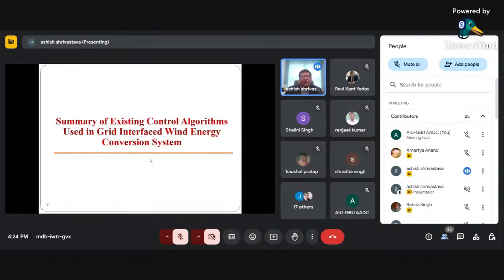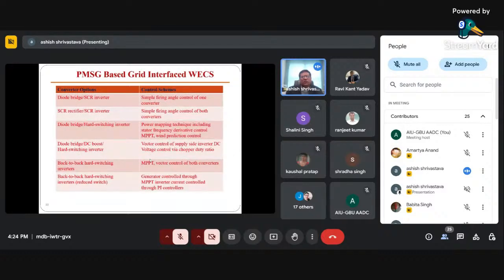So let me summarize the existing control in the grid interfaced wind energy conversion system. If you are using a PMSG, it can have a converter with a diode bridge or SCR inverter. The control is simple; firing control can be used. If you are using an SCR rectifier or SCR inverter, then you use firing angle control on both converters. If you are using a diode bridge or hard switching inverter, then we can use a power mapping technique, including stator frequency derivative control, that is MPPT or wind prediction control. If you are using a diode bridge or DC boost or hard switching inverter, then you can use vector control of the supply side inverter or DC voltage control via chopper duty ratio controlling.